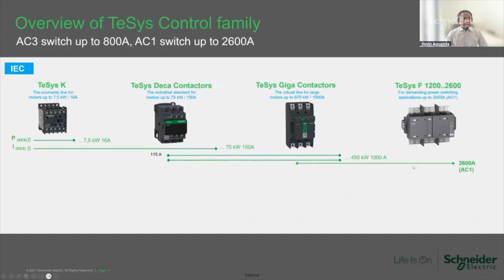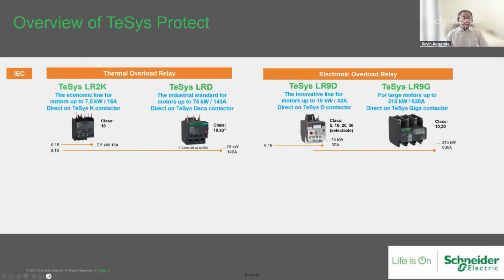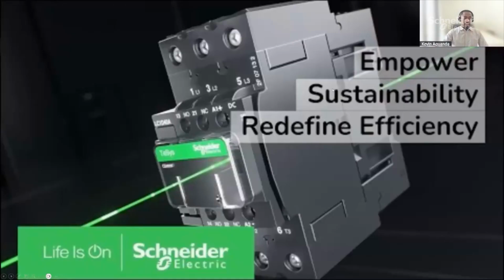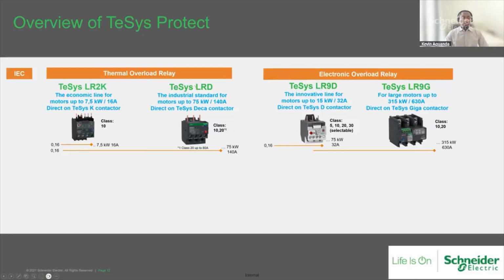For the contactors, it's the 4 ranges we've discussed under the TeSys umbrella for high performance applications, where we have TeSys K, Deca, Giga. The TeSys F range now only exists for much higher power requirements, from above 1,000 amps up to 2,600. Within the rating requirements of 100 amps to 800, this is the portion where we have our TeSys Giga range today. And when it comes to overload relays, for those 3 component applications, we have either thermal overload relays or electronic overload relays, set up to cover the full range of contactors that we provide today.